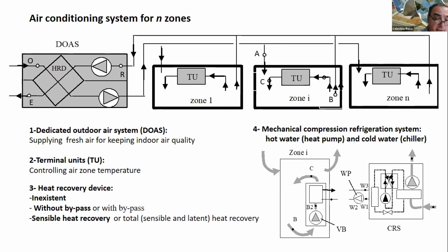The dedicated outdoor system is responsible for supplying fresh air to the different rooms. The terminal unit is responsible for controlling the indoor air temperature of the respective room. The terminal units are connected by a hydronic system to the centralized mechanical compression refrigeration system, which in heating mode operates as a water heater and in cooling mode as a water cooler, a chiller.